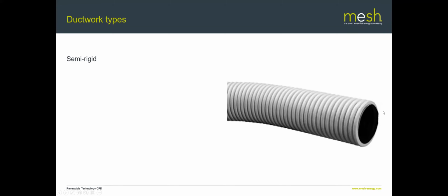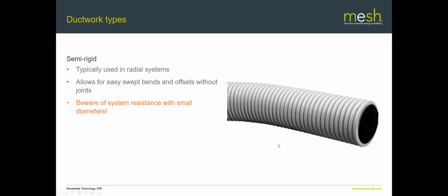Next up is the semi-rigid ductwork, which is what's used typically on radial systems. So as I said, this is sort of rigid, it feels a bit like a giant Hoover tube. So if you imagine that tube, you can't crush it easily. You can, but it is flexible within an extent, and for that, it's brilliant. It allows you to make small offsets and bends without having to have joints. But the downside is it can be a bit more resistance, especially in smaller diameters. Typically on a domestic system, that duct would be about 90 mil external diameter, so it can be quite a small diameter.